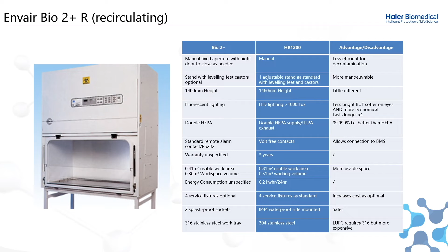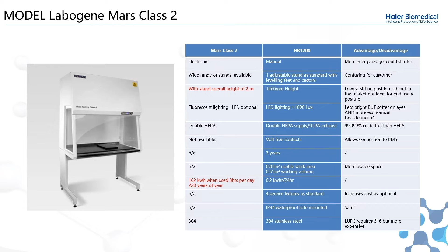This is the Labogene Mars Class 2 model. Some unique selling points against this product: we offer a manual sash as standard. Manual sashes have a much lower failure rate, are more energy efficient, and can be closed easily during a power failure. We offer an adjustable height stand with feet and casters as standard instead of multiple stands, making it easy to quote the customer. This allows for an adjustable working height that can easily be lowered or raised at point of installation for customer needs. We offer LED lighting as well as fixtures, IP44 rated side mounted plugs, and volt-free contacts as standard.